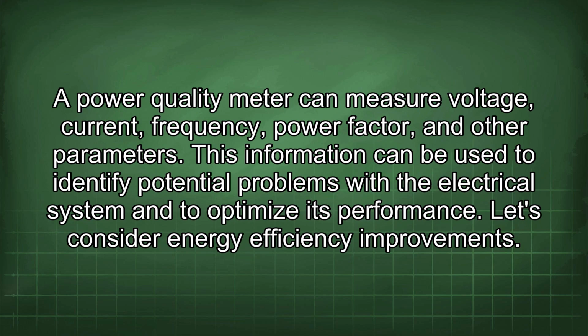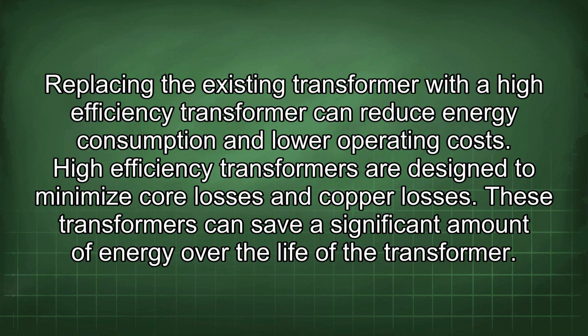Let's consider energy efficiency improvements. Replacing the existing transformer with a high-efficiency transformer can reduce energy consumption and lower operating costs. High-efficiency transformers are designed to minimize core losses and copper losses. These transformers can save a significant amount of energy over the life of the transformer.